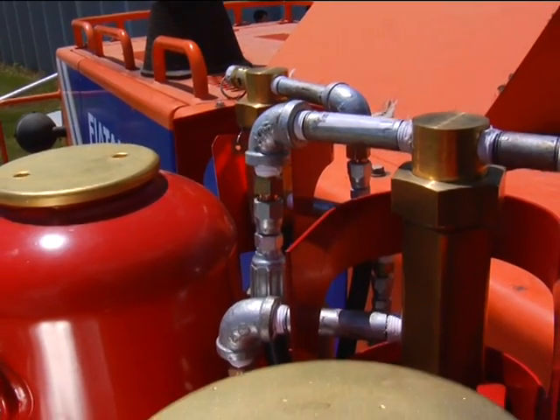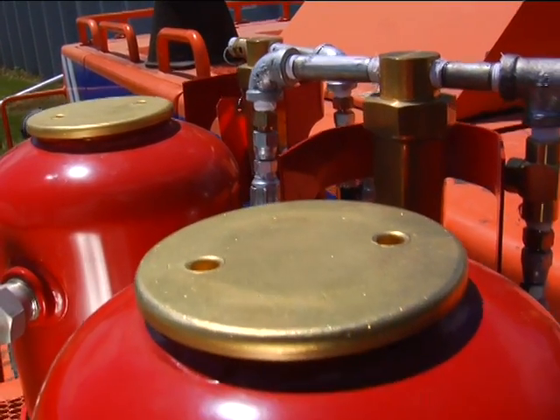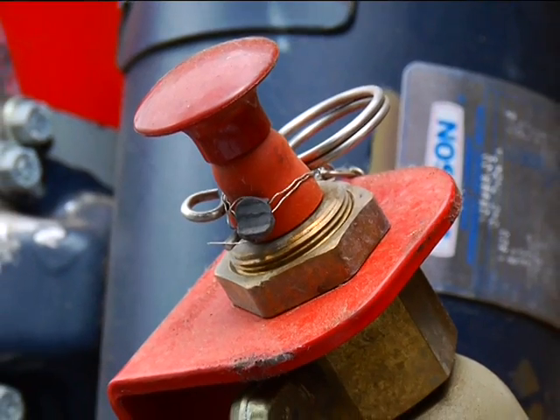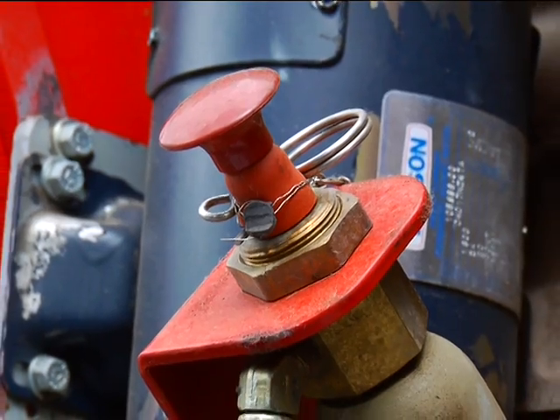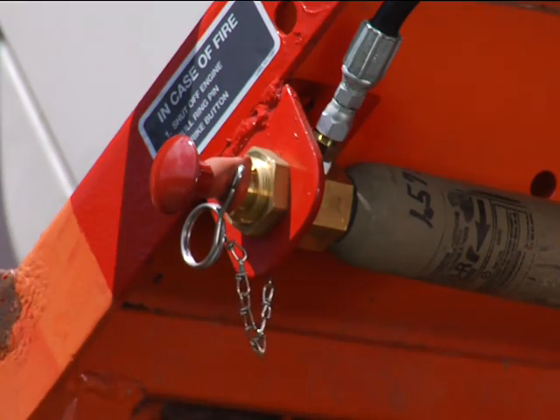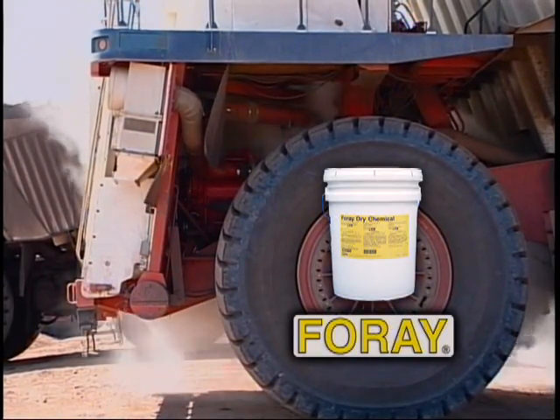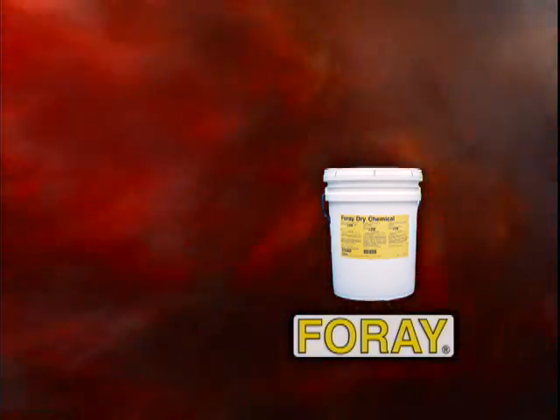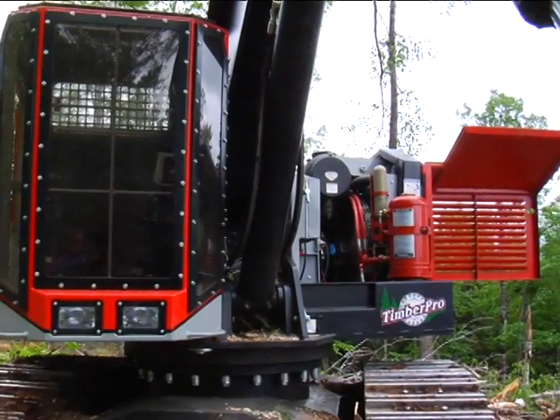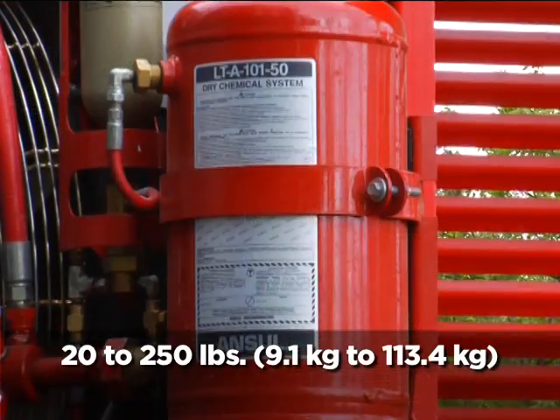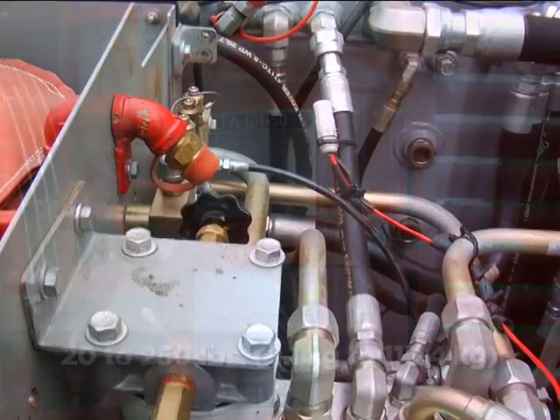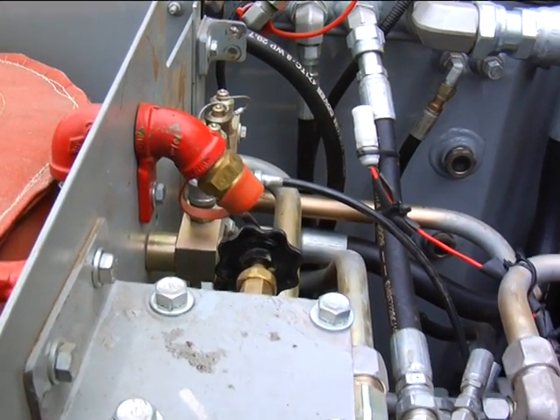A-101 systems are also equipped with backup manual actuation capability, with one or more pneumatic actuators located at points along the path of egress. The standard A-101 system is a dry chemical system that uses Ansul Foray multipurpose dry chemical. Tank capacities range from 20 to 250 pounds. Nozzles have a fixed aim and are designed to flood the hazard area.